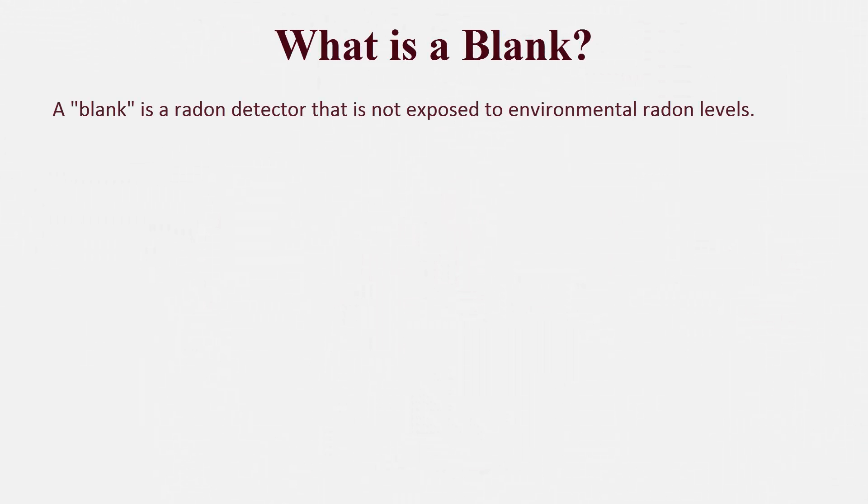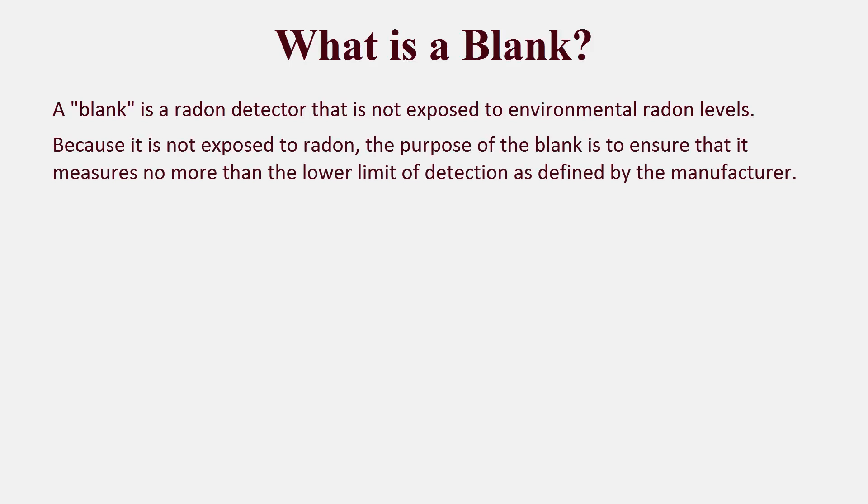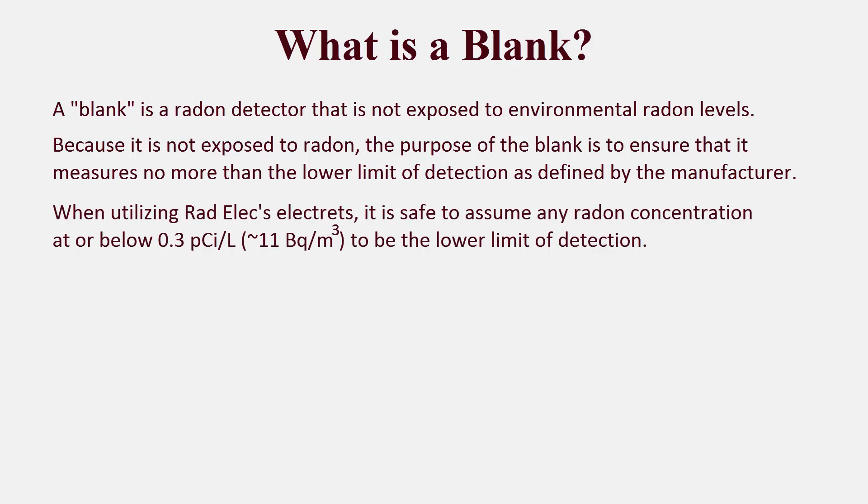What is a blank? A blank is a radon detector that is not exposed to environmental radon levels. Because it is not exposed to radon, the purpose of the blank is to ensure that it measures no more than the lower limit of detection as defined by the manufacturer. When utilizing Radelec's electrets, it is safe to assume that any radon concentration at or below 0.3 pCi per liter, or approximately 11 becquerels per cubic meter, to be the lower limit of detection.